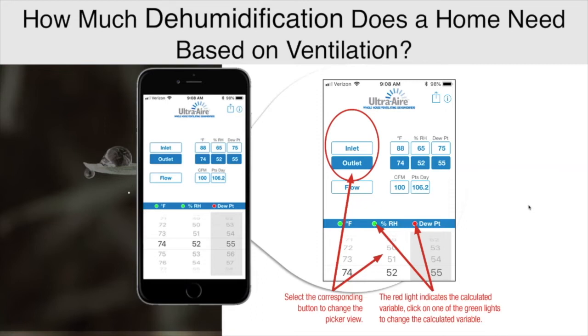So 88 degrees outside, 65% RH, which is a 75-degree dew point. The outlet, what I want in my home, in the example here, is 74 degrees, 52% RH, and a 55-degree dew point. And the flow is the CFM. That's my ventilation rate. So based on those conditions, this is telling me at a ventilation rate of 100 CFM, I'm going to need about 106 pints of water removal a day.